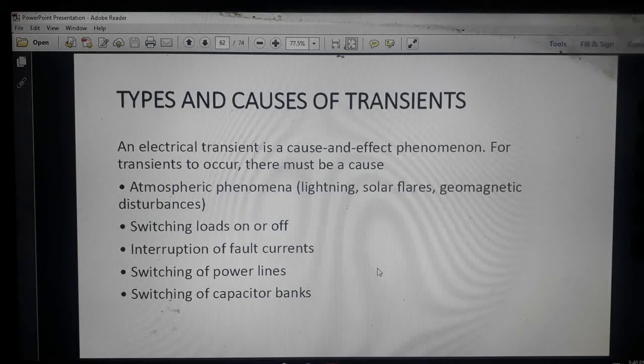Next is switching load on or off. Loads are of two types, but basically most loads are inductive. If a highly inductive load is disconnected from our distribution system, then an over voltage transient may be generated for a minimum time duration. If we connect a capacitor bank for improvement of the power factor, it may lead to generating transient over voltage. These are the causes by which transient over voltage is generated.